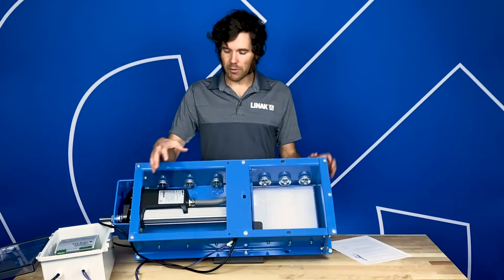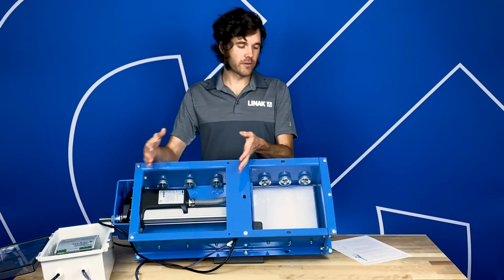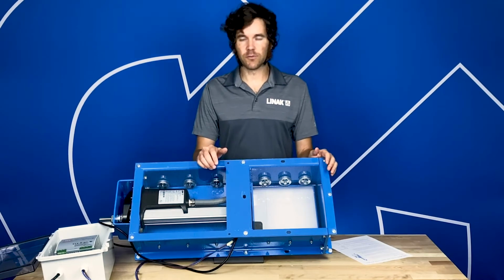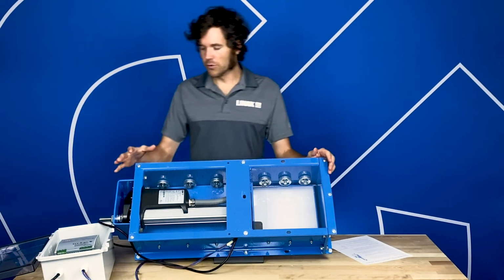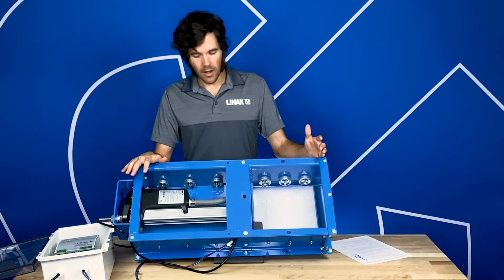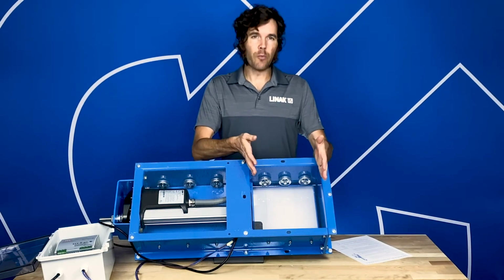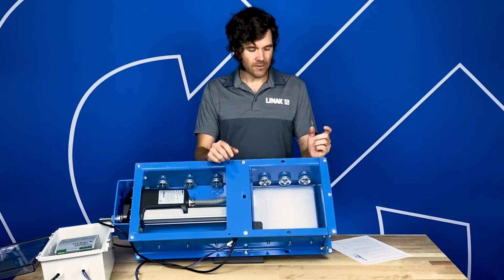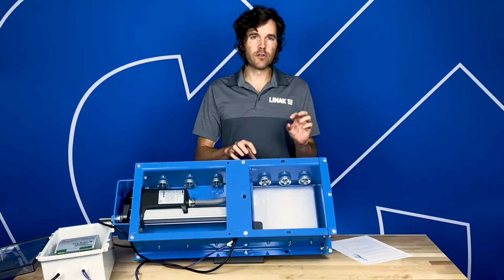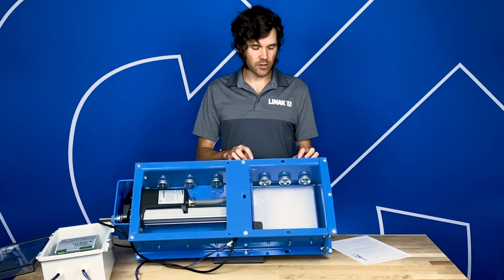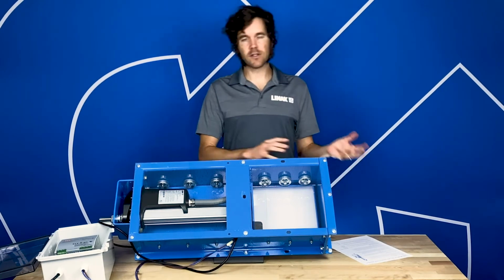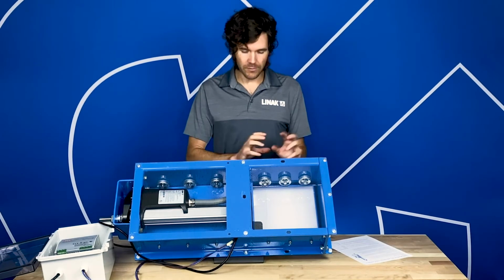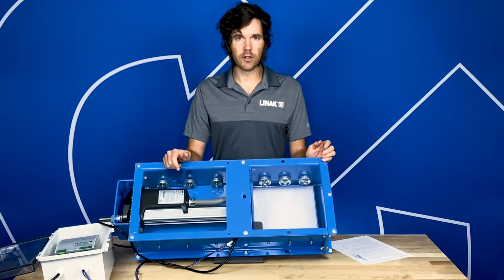Because our actuator has certain dimensional tolerances, and the welded structure of a slide gate can have varying tolerances as well, it's important to be able to have the actuator run to that specific opening without going to its full current cutoff. Typically in the past with slide gates, you might have external proximity switches added to the structure, but that adds a level of complexity to the system, as you have to have more hardware and the possibility of damage if they're not working correctly.